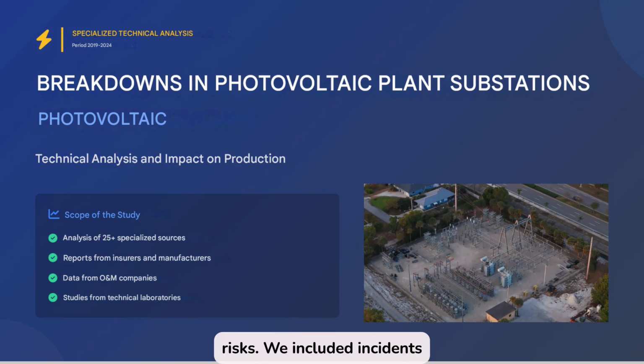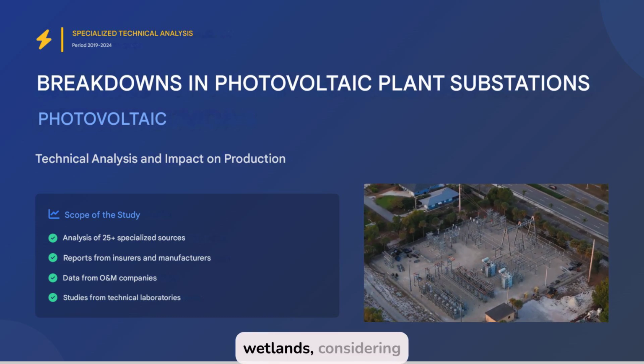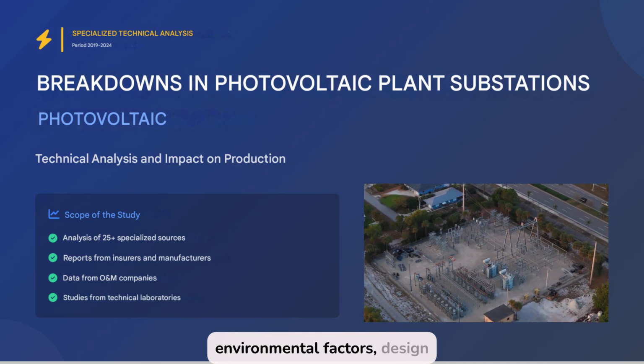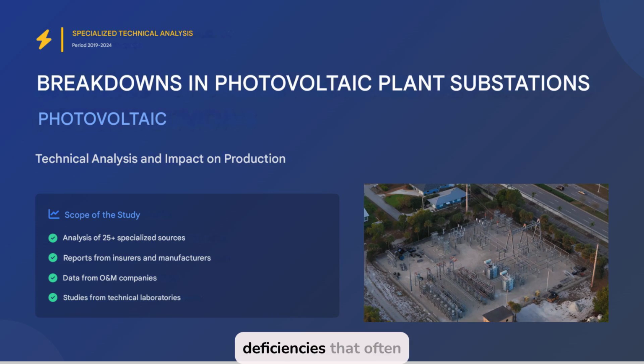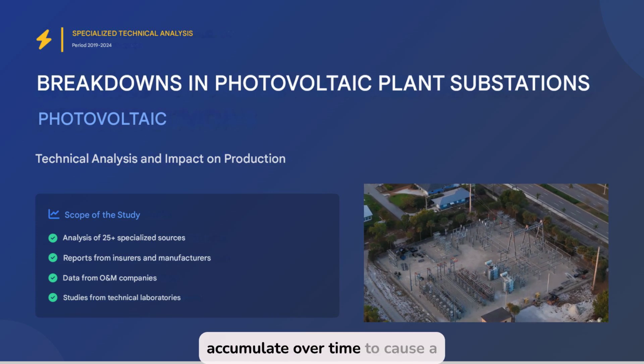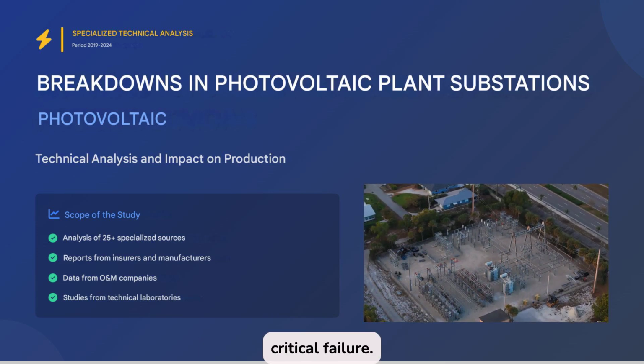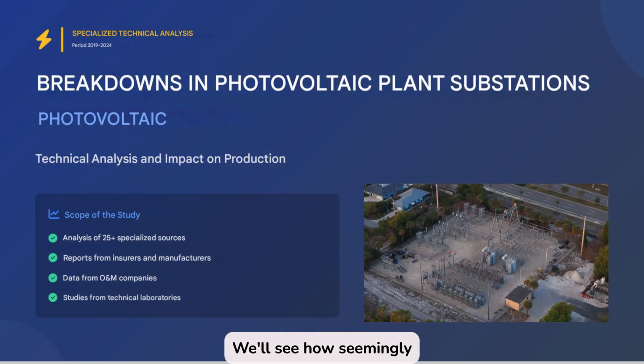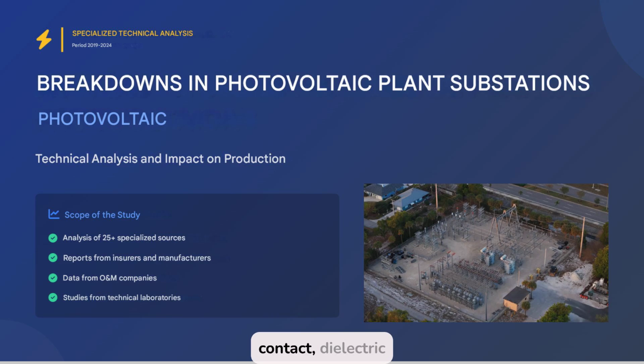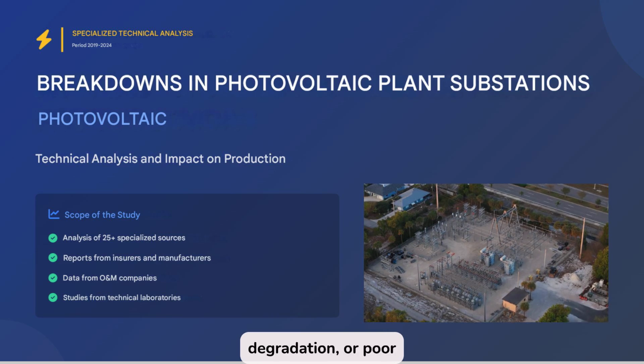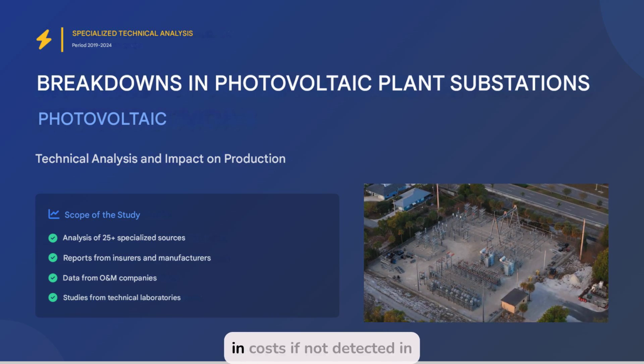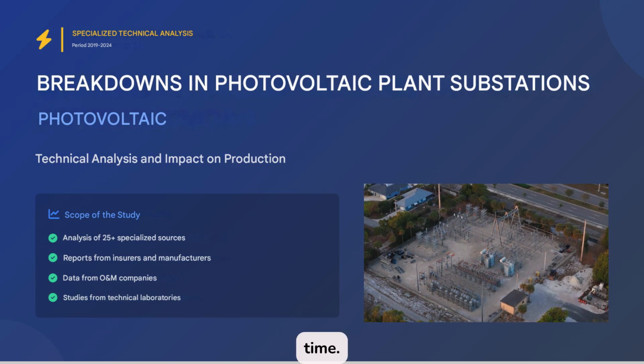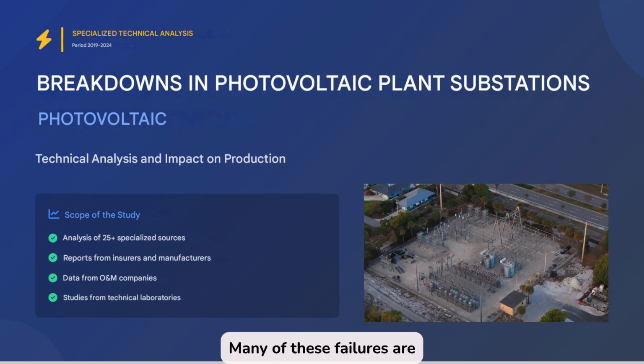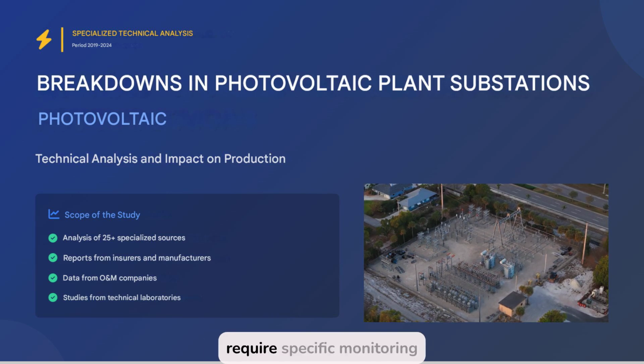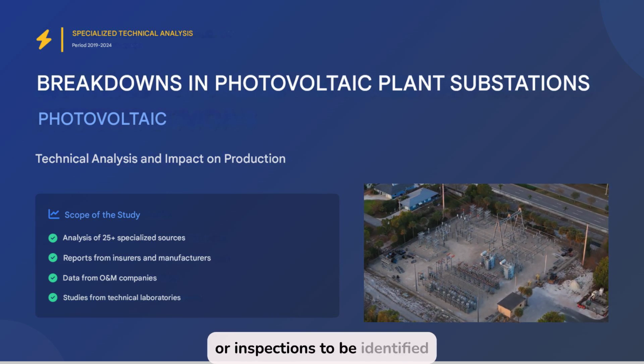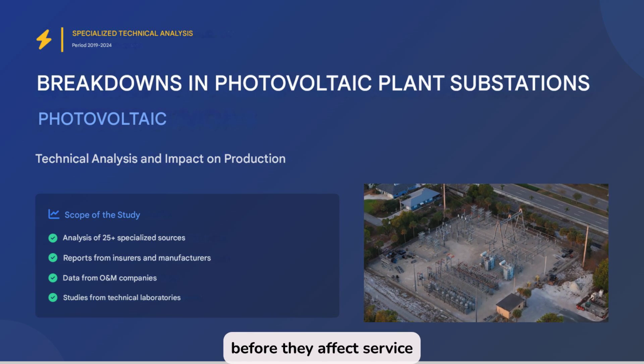We included incidents in both desert and wetlands, considering environmental factors, design errors, and maintenance deficiencies that often accumulate over time to cause a critical failure. We'll see how seemingly small failures, such as loose contact, dielectric degradation, or poor insulation, can escalate in costs if not detected in time. Many of these failures are invisible to the human eye and require specific monitoring or inspections to be identified before they affect service continuity.